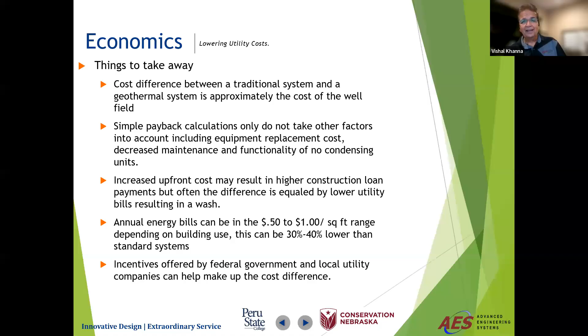Sometimes if there's a residential facility, you can give some backup supplemental heat. When we first started using geothermal systems 20-plus years ago, some projects did have backup boilers, but we never used them. As we gained confidence in our designs, that went away. So most of our newer systems, we don't even use glycol - we don't even expect the water to freeze. Sometimes we use it if calculations tell us we really need it, but otherwise we don't use glycol or supplemental heat. But for safety factor or insurance purposes, if you really wanted to put something in, we have done some sort of supplemental heat - electric resistance heat, gas-fired duct heaters. We haven't done that too much, but it can be installed as well.